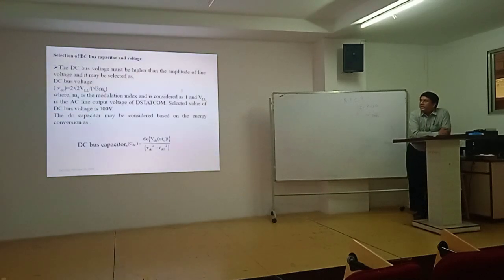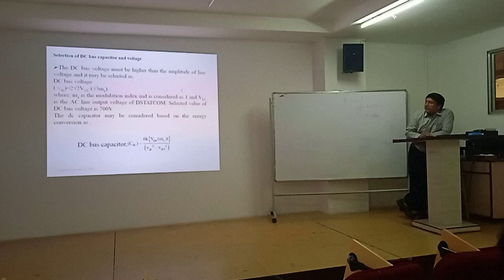Next is how we can design the DC bus voltage. The DC bus voltage formula is 2 root 2 V line to line divided by root 3 into MA. Based on this formula, we can design the DC bus voltage. So this is for calculation purpose only. Suppose supply voltage 415, you can calculate. Some value will come.